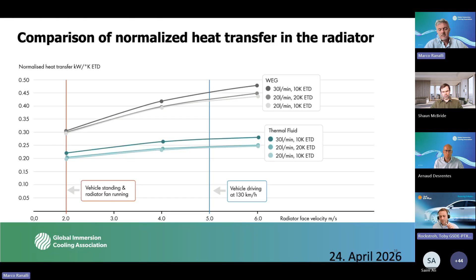What you can see is it's by no means half—it's around 70%, 73% in fact, of the heat rejection rate of the radiator that's still achieved with the thermal fluid. That's borne out by the fact that in the overall system there's thermal resistance between the fluid and the surface, then conduction through the aluminium which is negligible, but the surface-to-air rejection rate is pretty poor because air is a very poor heat conductor. That mutes the overall loss in thermal heat transfer coefficient—it's masked by the fact that we have to reject to the environment, so it doesn't look all that bad.